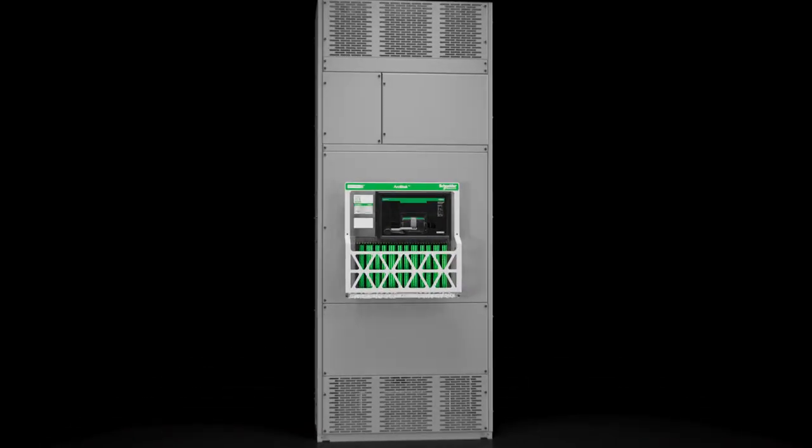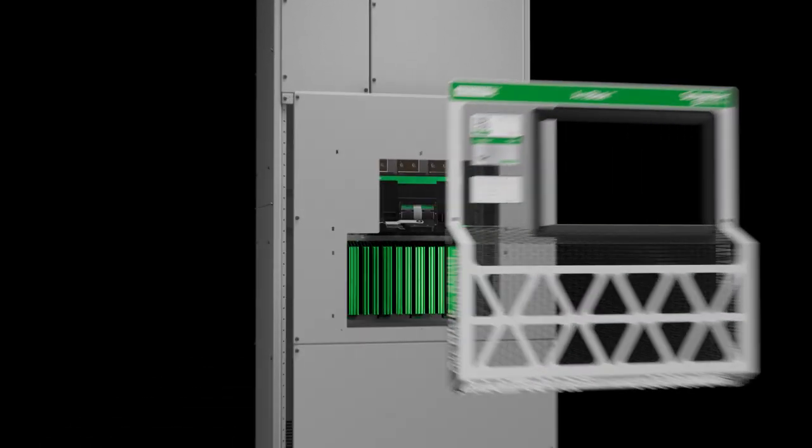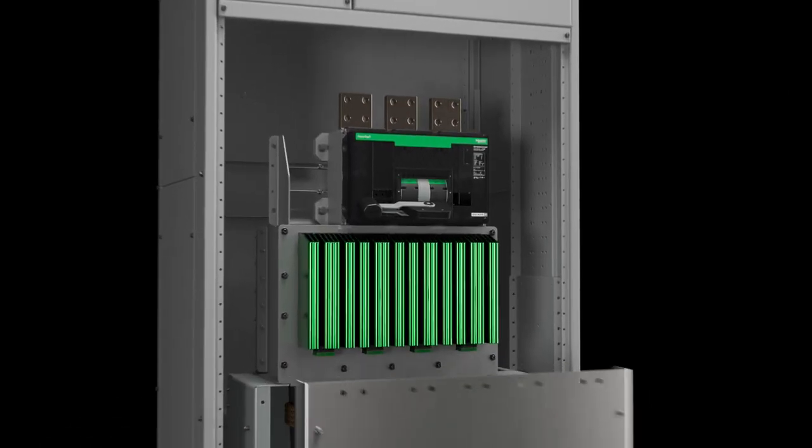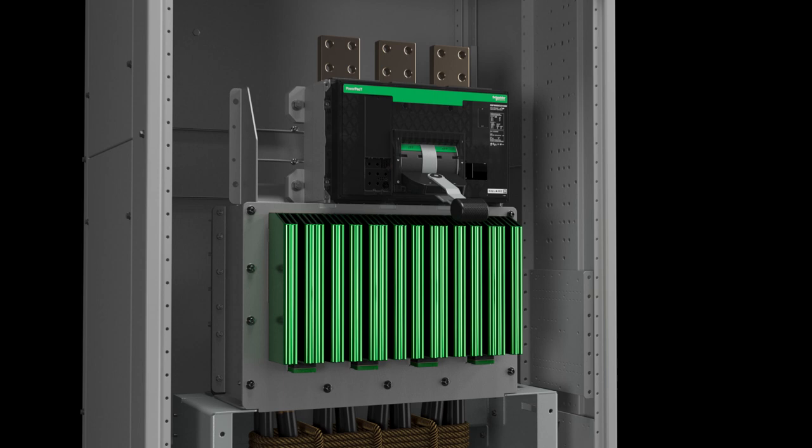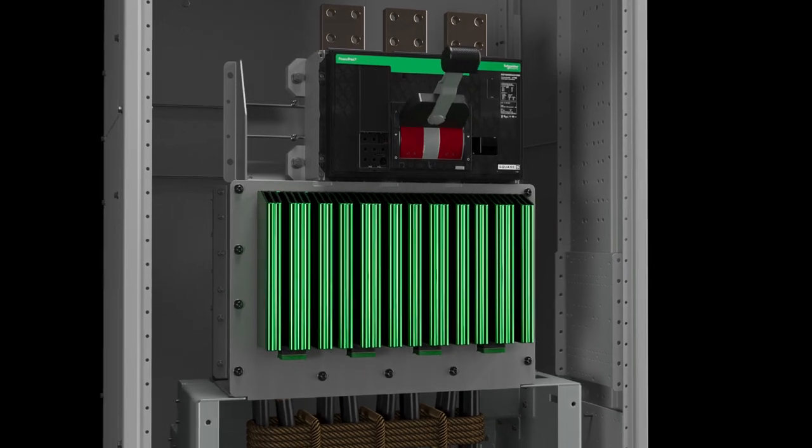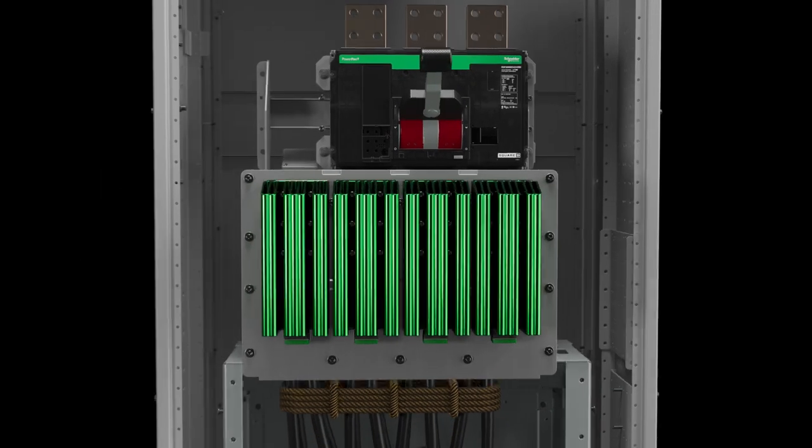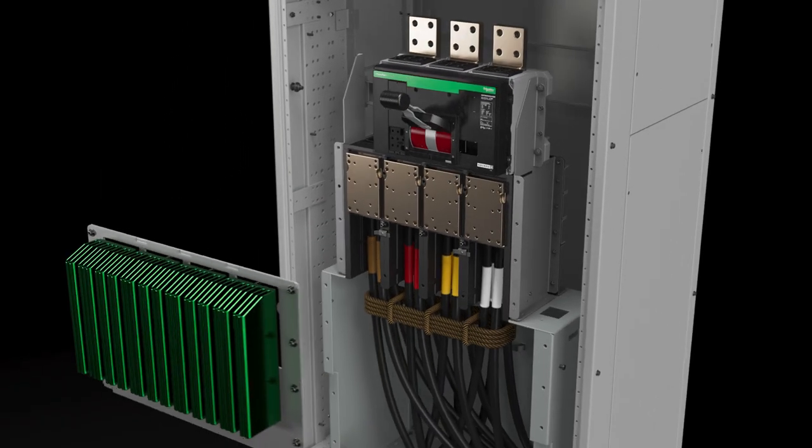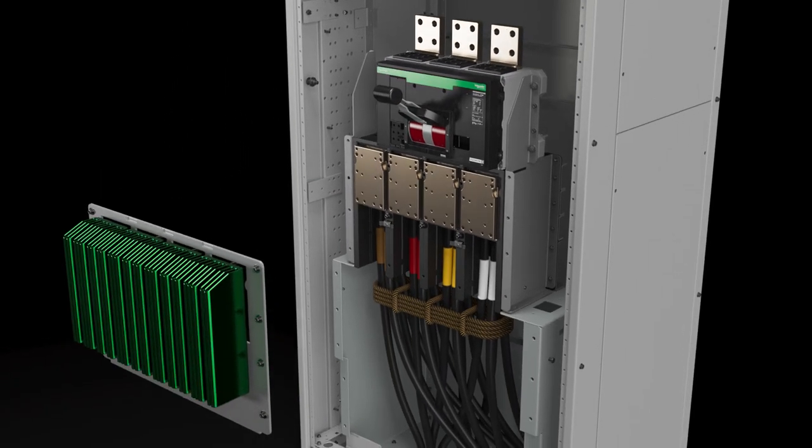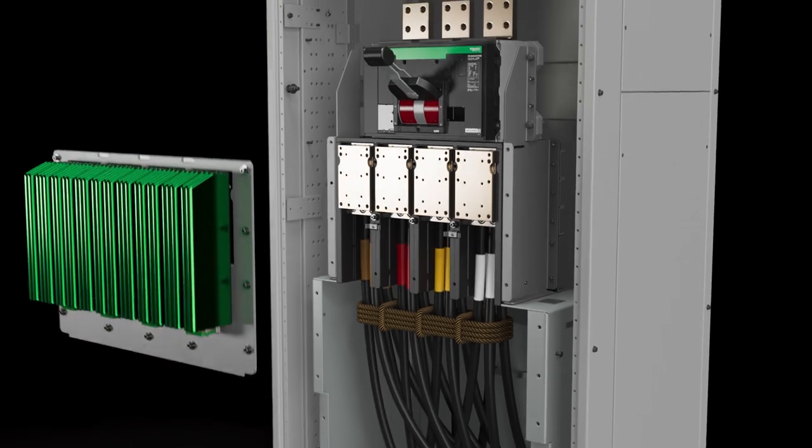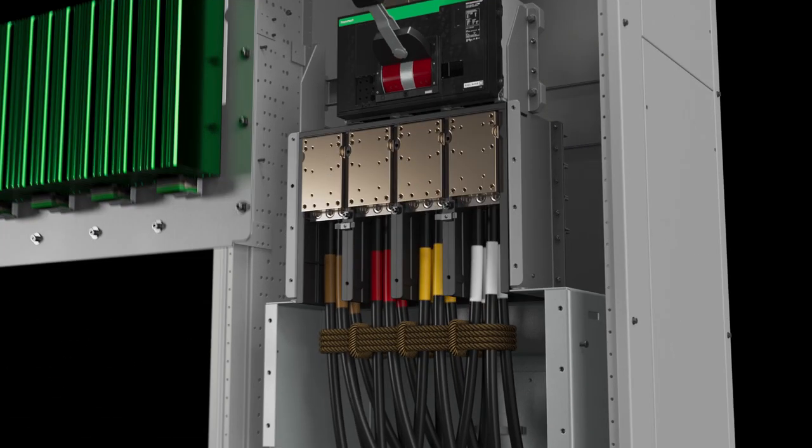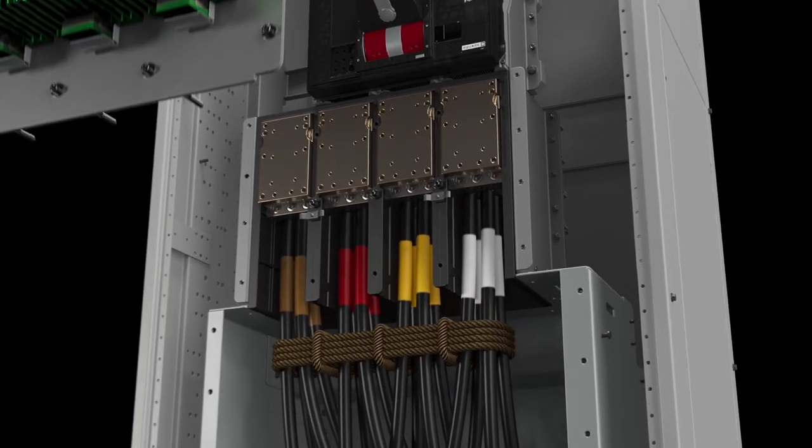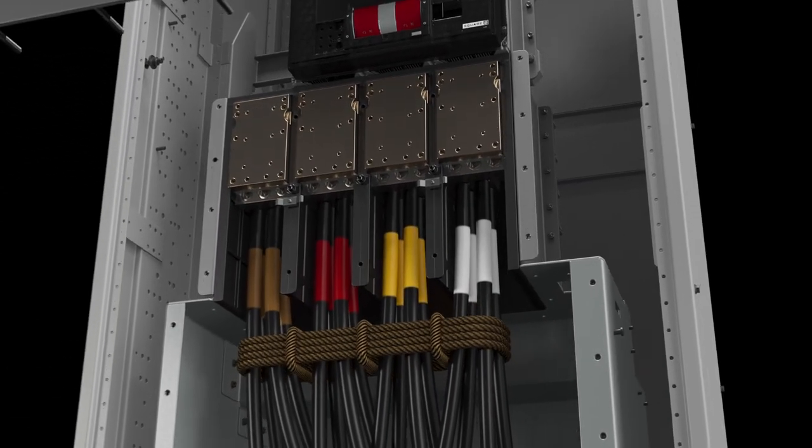A major cause of arc flash events in electrical installations is poor power connections caused by improper tightening, vibration, or damaged contact surfaces due to corrosion or excessive pressure.